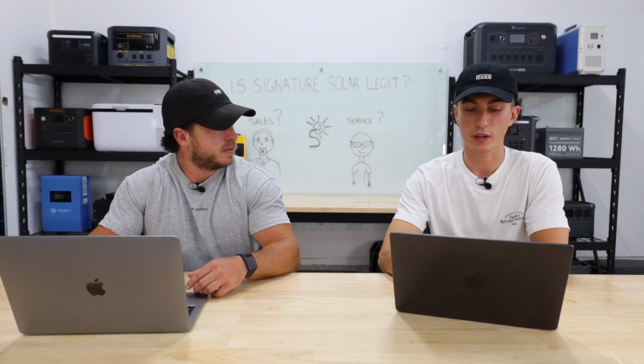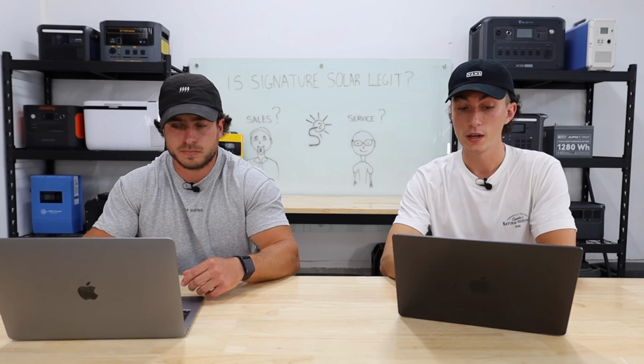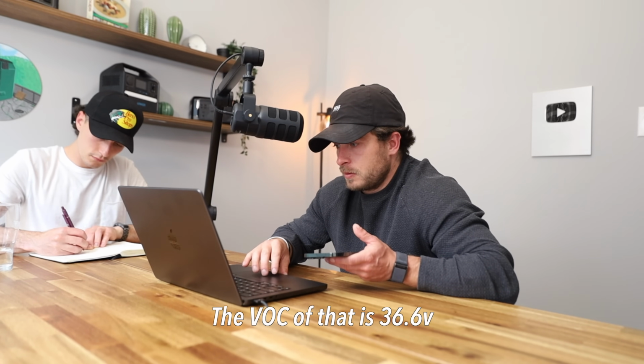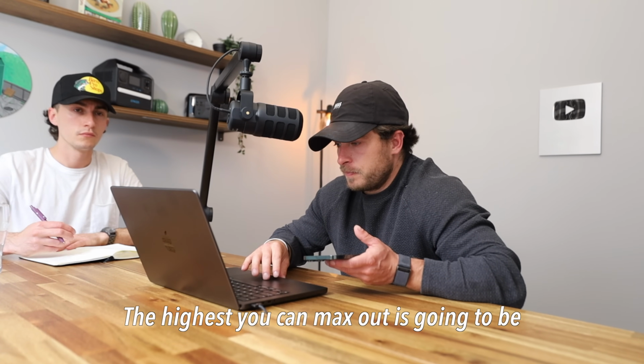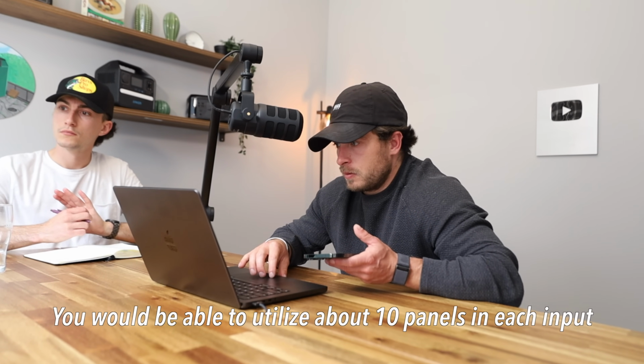Oh, okay. Sorry, my wife's just on the other end of the table here. She recommended a 7.9 kilowatt array, so it would charge your whole system in 4 hours. She explained how they match with the inverter. The VOC of that's 36.6 volts. With the 6000 XP, the highest you can max it out is going to be 385. You would be able to utilize about 10 panels in each input, so you could do 20 of those Canadian Solar 395s. And then she collected my info for the quote.